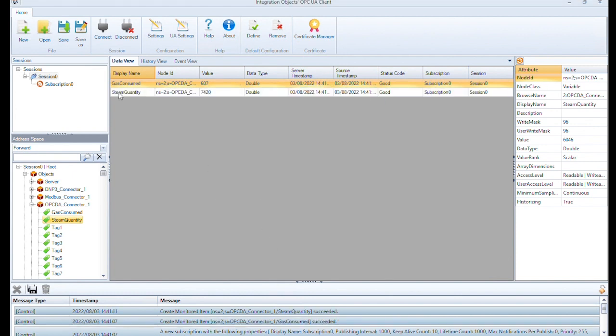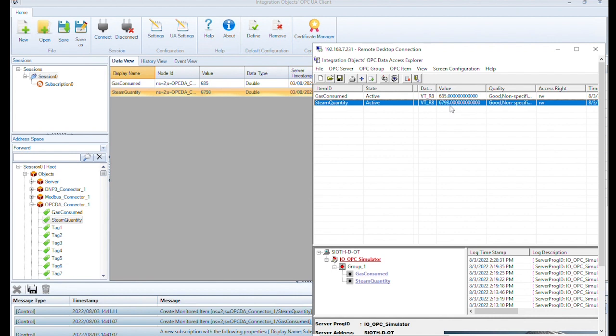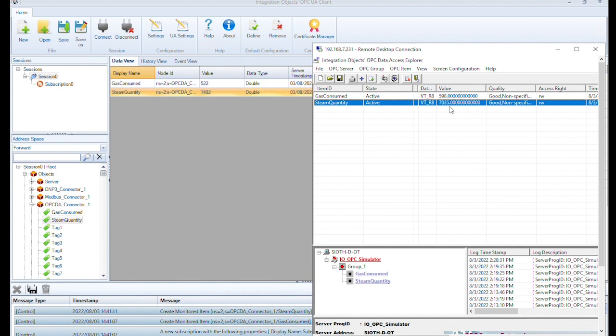We can compare the values received on the SIOT OPC UA server with the ones from the source OPC DA server. Using OPC DA Explorer, a test OPC client, we can see that the values displayed in the OPC UA client are the same.